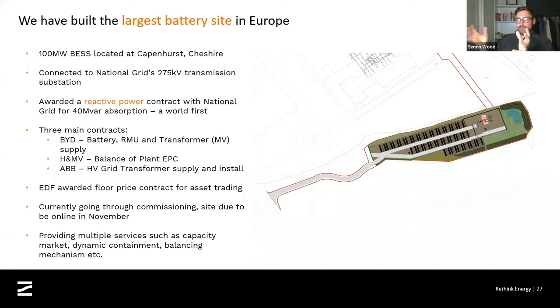And just to give you a flavour of how we'd go about delivering this, we generally split it into multiple contracts. We don't operate on a full turnkey EPC type basis, where we employ a single contractor to deliver everything regarding that project. We split the contracts up. So we'll have some supply contracts for key components, such as the batteries, the inverters and the large step-up transformers. Then we'll provide a balance of plant contractor with a wider role to piece it all together, essentially. They'll do all of the ancillary equipment installation, all of the cabling works and civils on site.